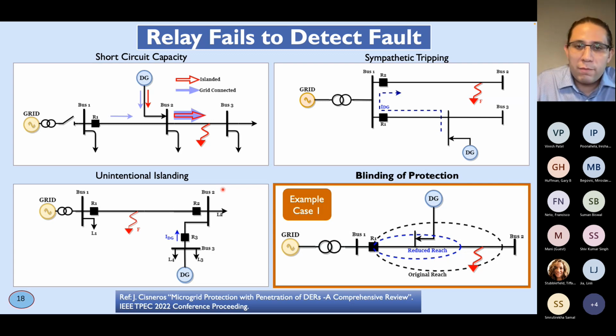In this case, I will talk about the blinding of protection. We know the short circuit capacity, sympathetic trip, and unintentional islanding. For blinding of protection, basically, we have a fault.